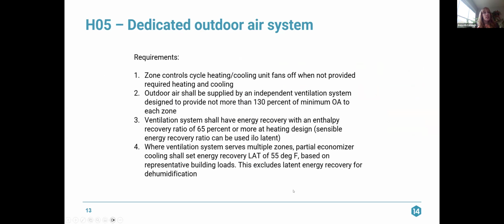So the requirements of section of credit H05 are that your zone controls have to cycle the heating and cooling unit fans to off when they are not providing required heating and cooling. So what they're looking for here is to have the DOAS, your ventilation system, providing ventilation air completely separate from your zone units, those VRF units, your fan coil units, whatever you have.